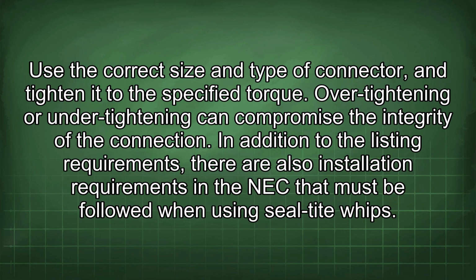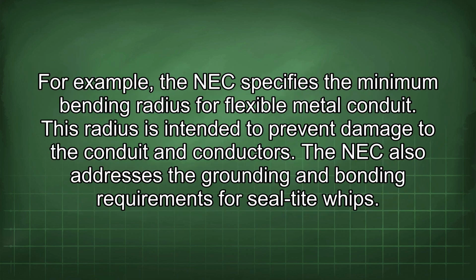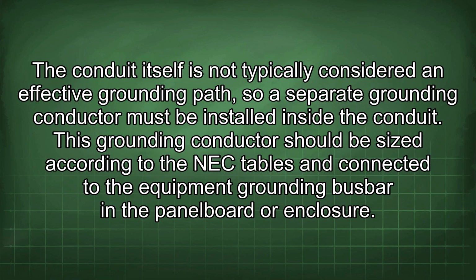In addition to the listing requirements, there are also installation requirements in the NEC that must be followed when using Seal-Tite whips. For example, the NEC specifies the minimum bending radius for flexible metal conduit. This radius is intended to prevent damage to the conduit and conductors. The NEC also addresses the grounding and bonding requirements for Seal-Tite whips. The conduit itself is not typically considered an effective grounding path, so a separate grounding conductor must be installed inside the conduit. This grounding conductor should be sized according to the NEC tables and connected to the equipment grounding busbar in the panel board or enclosure.